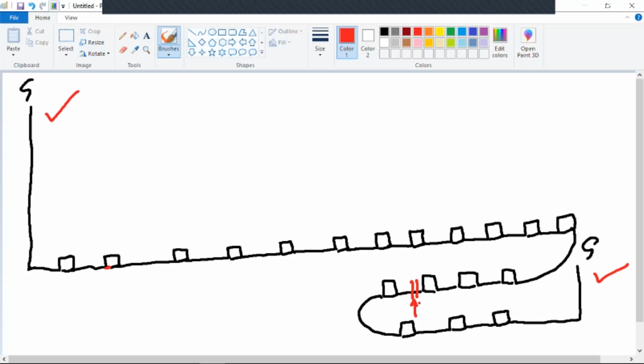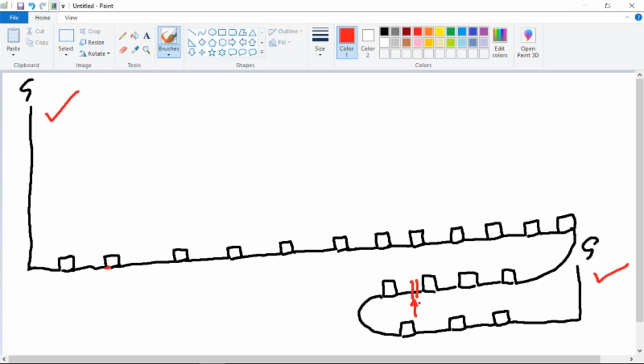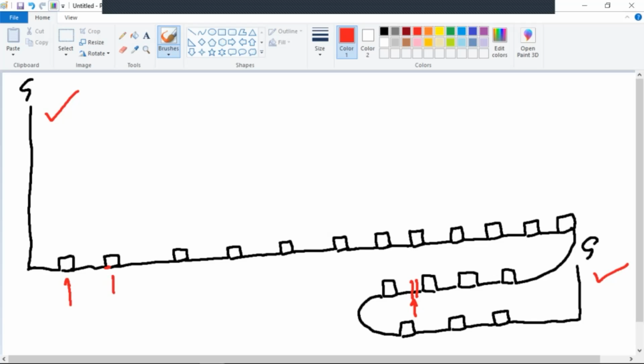Now, typically when you go out and start a brand new build in a subdivision, you're going to install a lot of transformers, and the homes aren't going to be built yet. So you're going to have a lot of transformers out in the field with fault indicators in them, going from transformer to transformer to transformer. And especially when you get down towards the end here, you're going to run into the situation we talked about before. How many amps does it take to reset an indicator? Do you remember what we said just a little while ago?